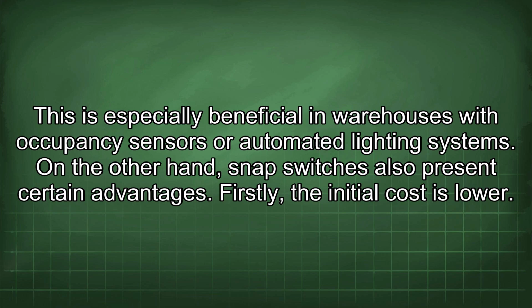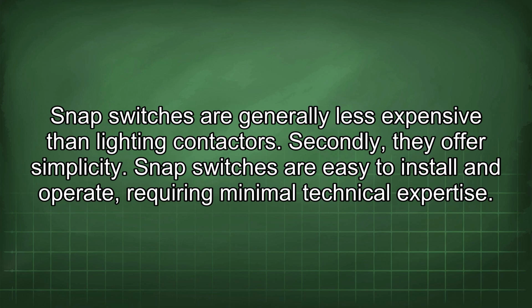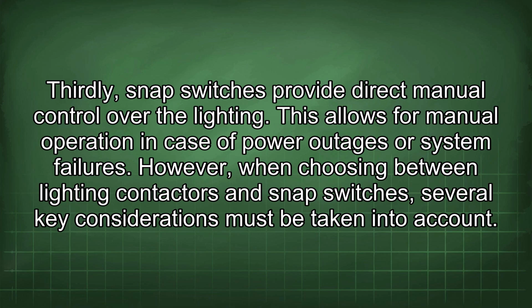On the other hand, snap switches also present certain advantages. Firstly, the initial cost is lower. Snap switches are generally less expensive than lighting contactors. Secondly, they offer simplicity. Snap switches are easy to install and operate, requiring minimal technical expertise. Thirdly, snap switches provide direct manual control over the lighting. This allows for manual operation in case of power outages or system failures.